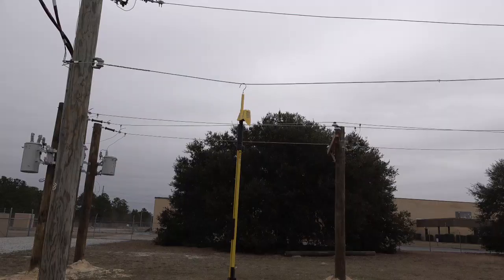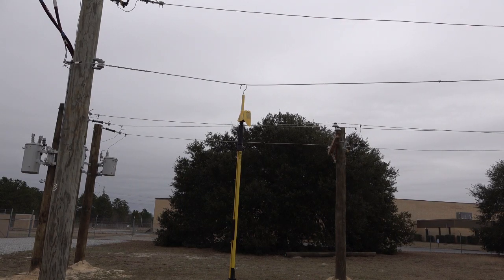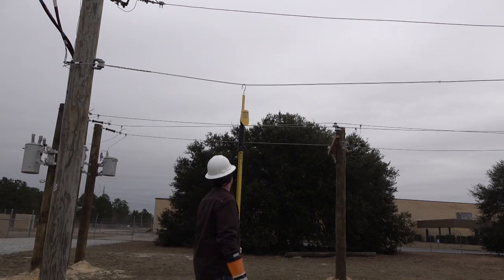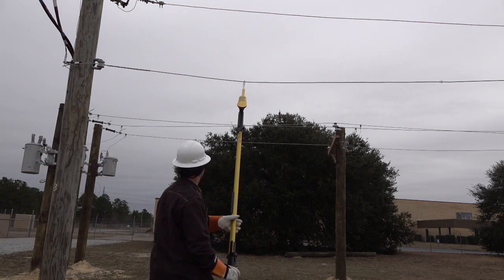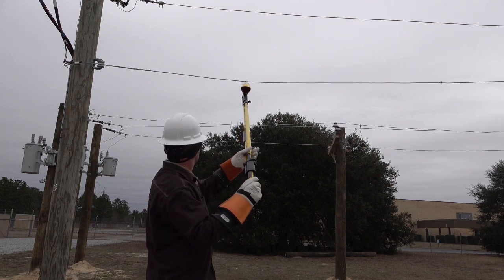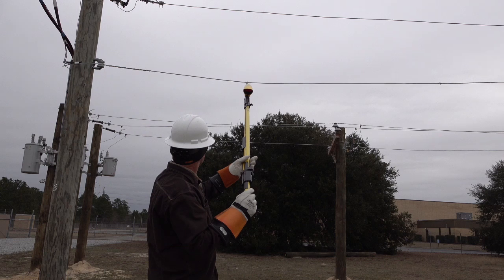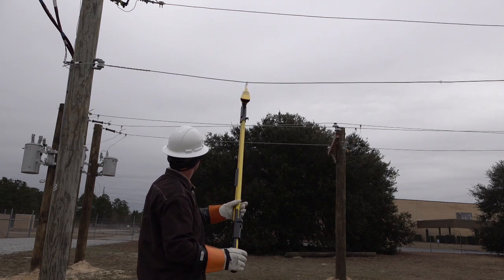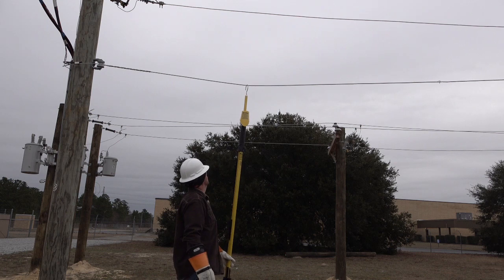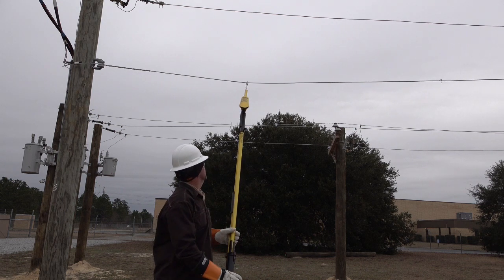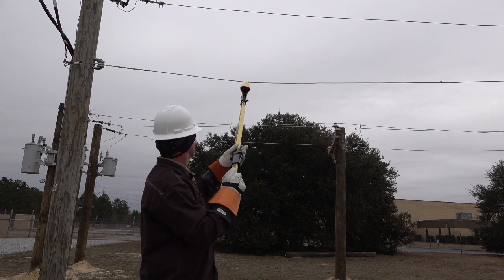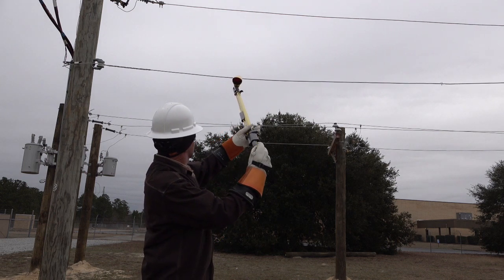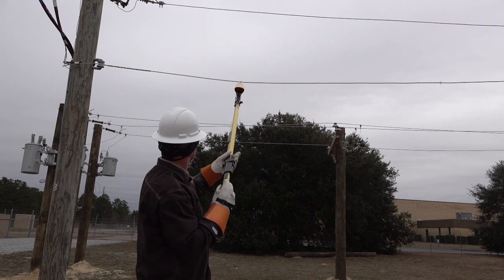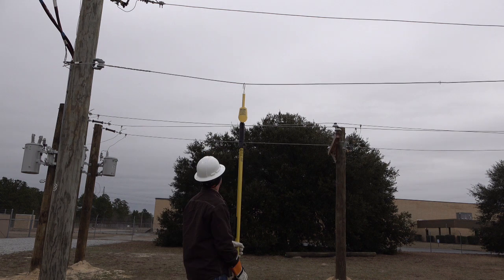I wanted to also demonstrate what can happen if you hang the VD1000 on a neutral wire or a ground wire down a pole. That doesn't mean there's a potential on the neutral wire. It only means that the meter is now trying to capacitively couple to the potential above it. All single probe devices will do this, so it's very important to understand that you must correctly orient the VD1000 or any other single probe device when you're working around a potential or a ground plane. So as long as the meter probe is oriented in the down position away from potential, the reading should be 0 on the display.